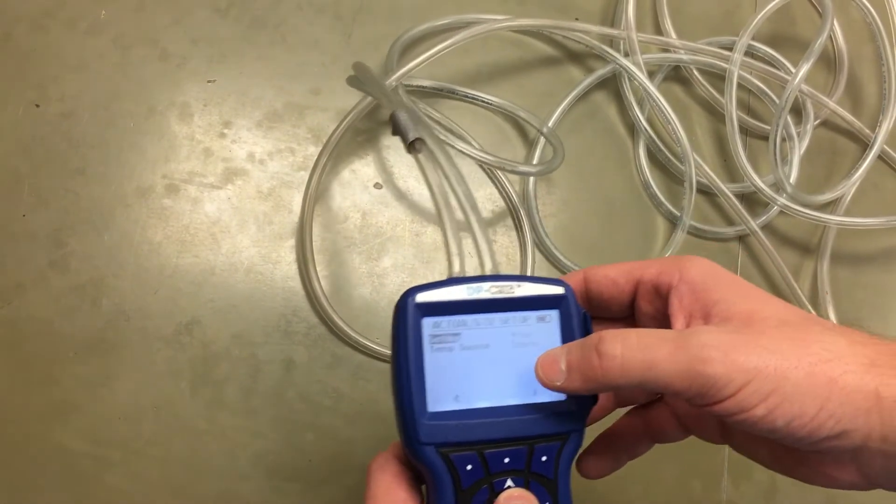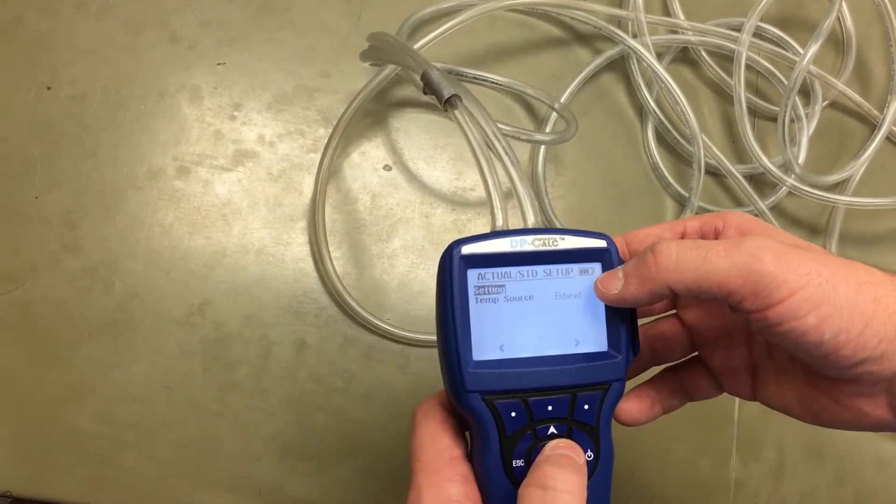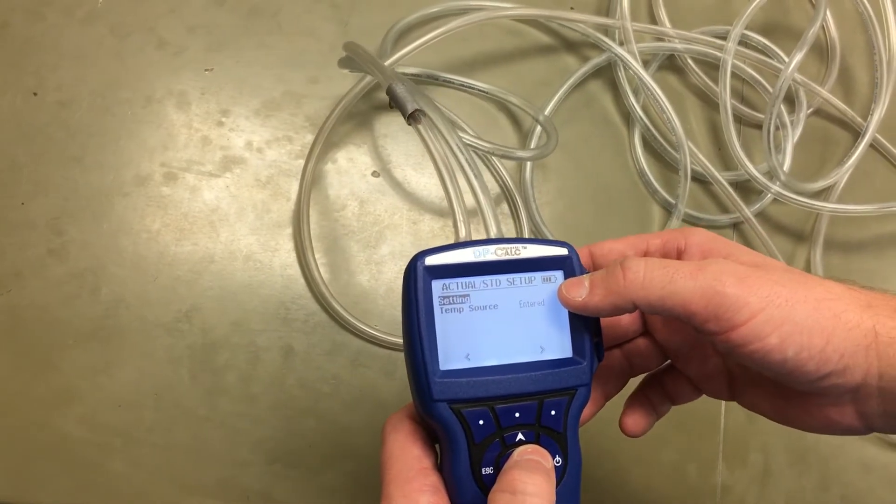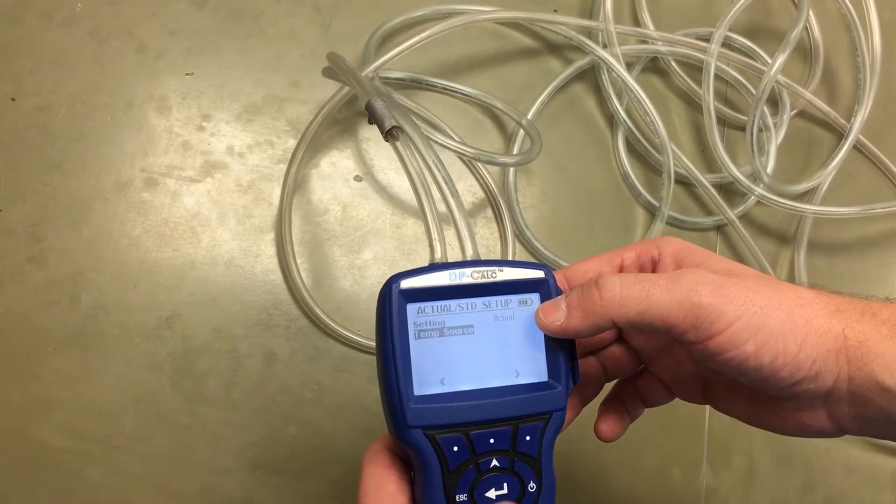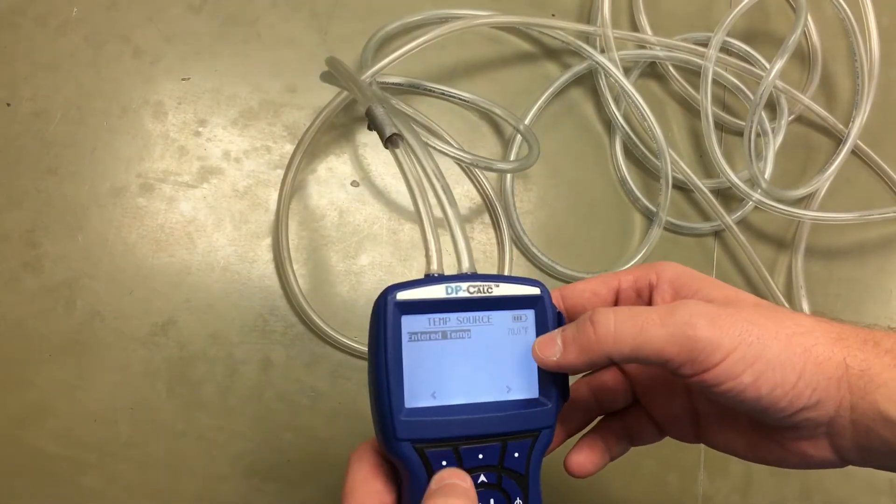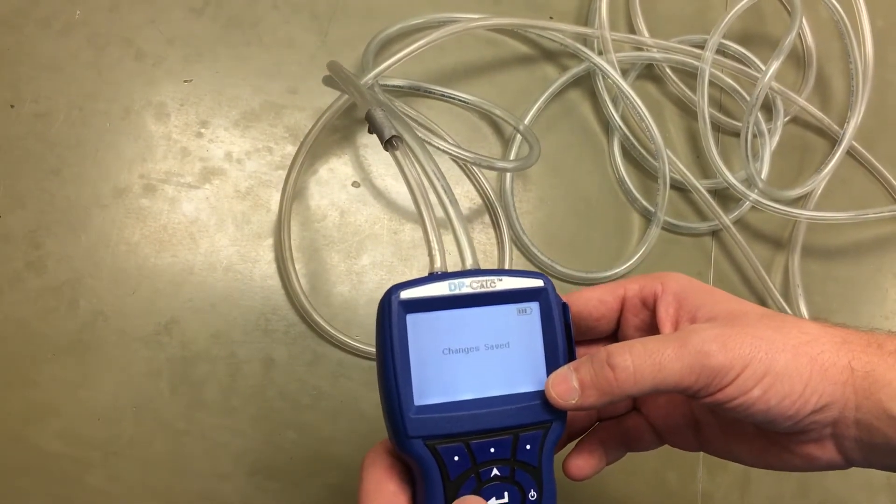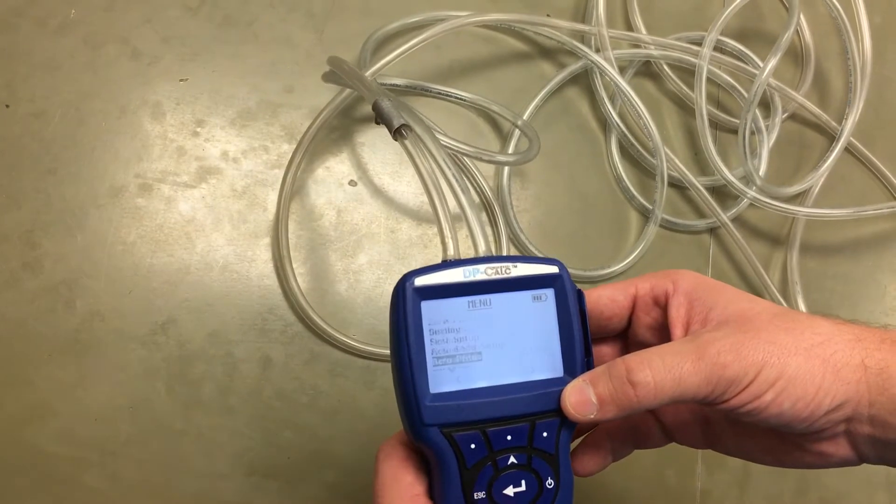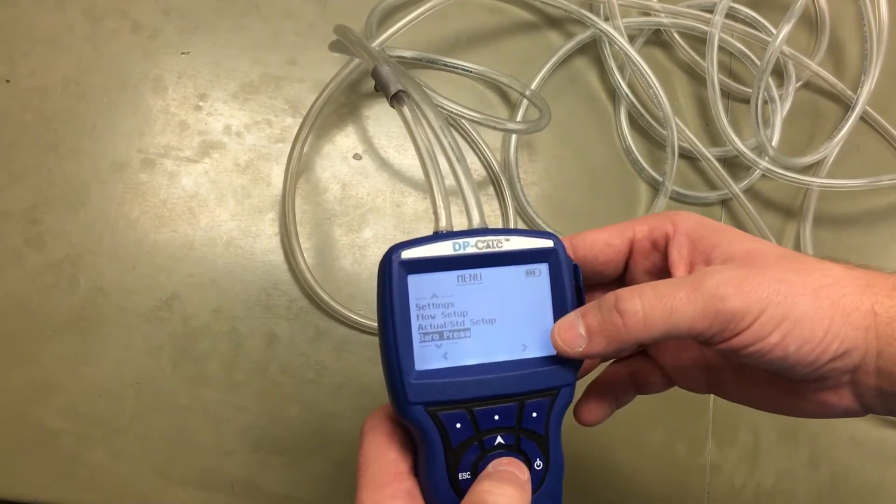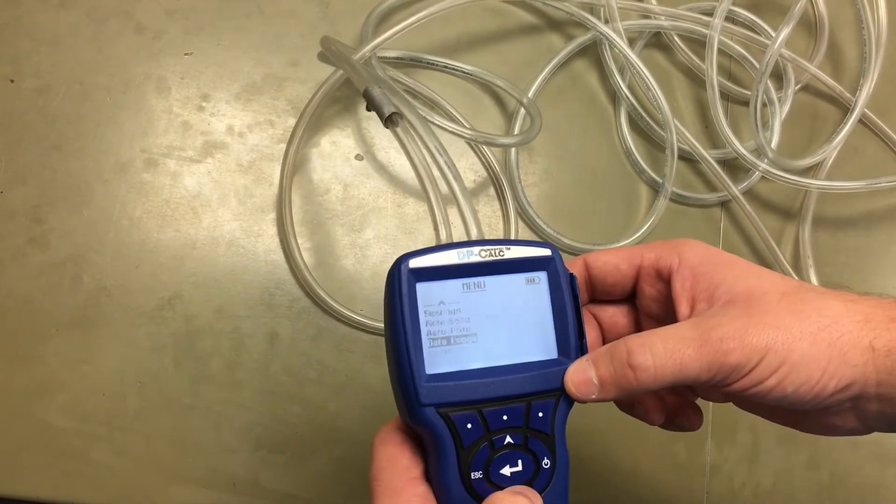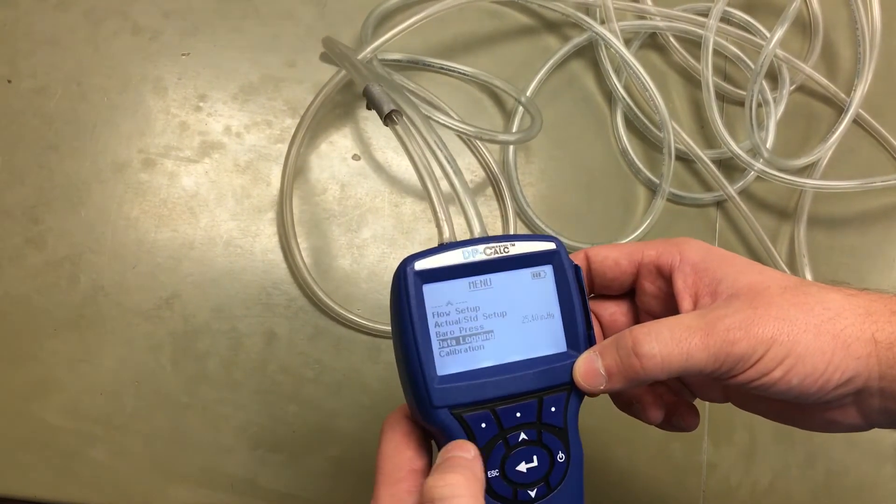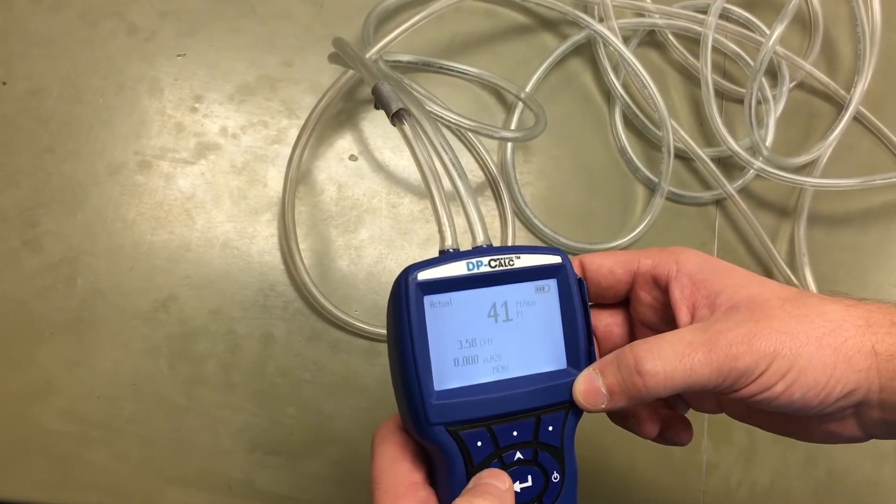Select either actual or standard. We're going to have it measure actual pressure so that we don't have to adjust our measurement for the pressure at our altitude. Set the temperature to 70 degrees and set the barometric pressure, which at our location is 25.4 inches of mercury. We're ready to measure.